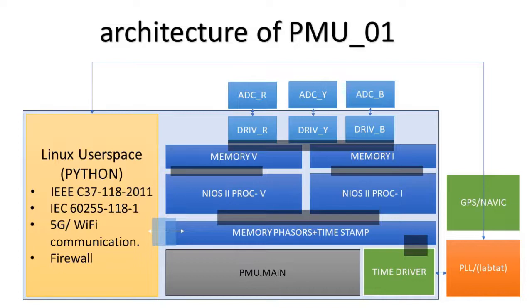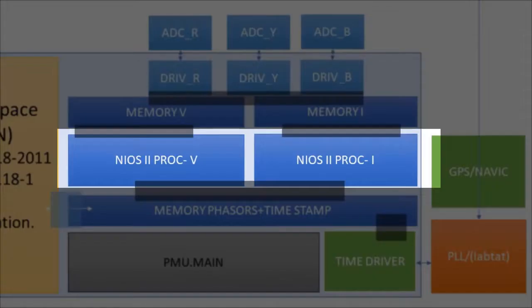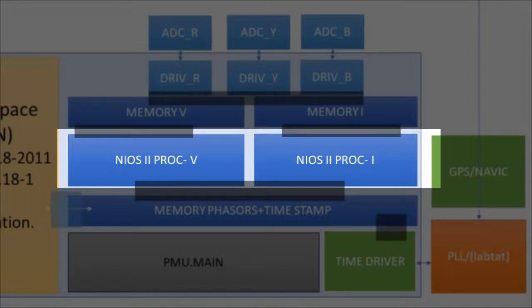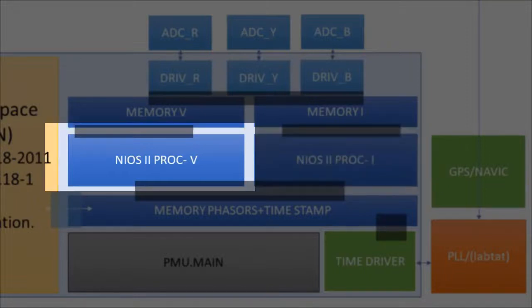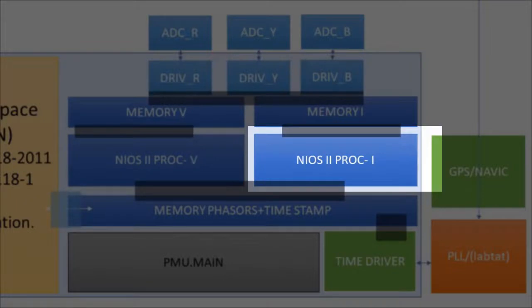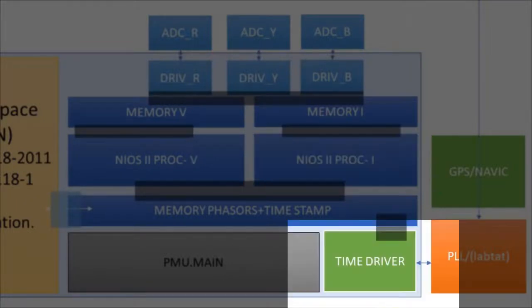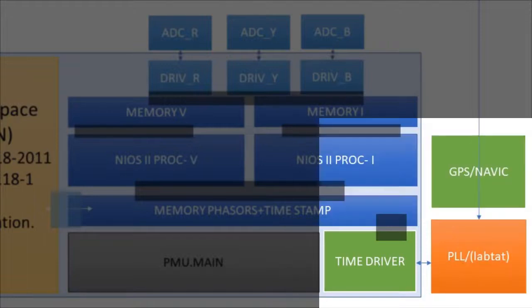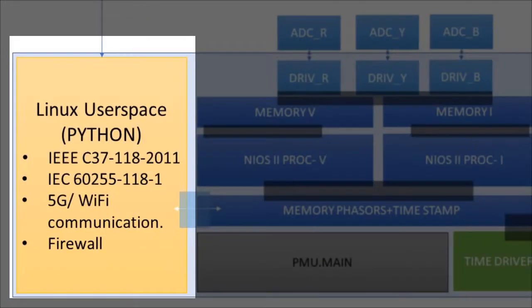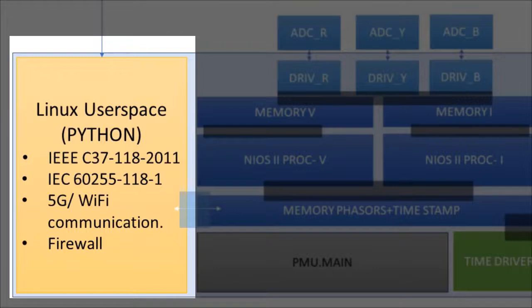As for 100 measurement reports per second, we have a time cost of only 10 ms. For phasor processing, it has two separate cores which run parallelly. One processes three-phase voltage samples and the other three-phase current samples. It is also equipped with a separate core time driver which is responsible for timekeeping by using timing data from NAVIC receiver module. This SoC also has an ARM Cortex-A9 based Linux processor which deals with communication of phasor data to PDC through internet.